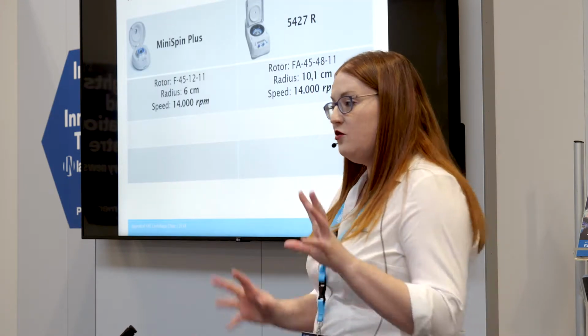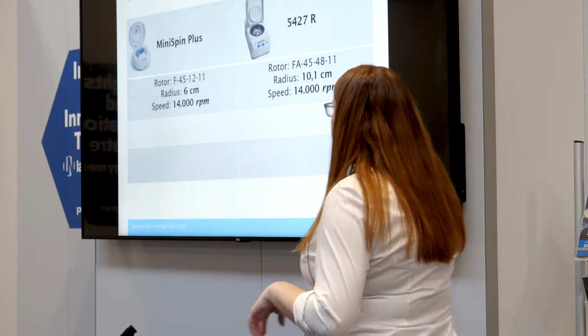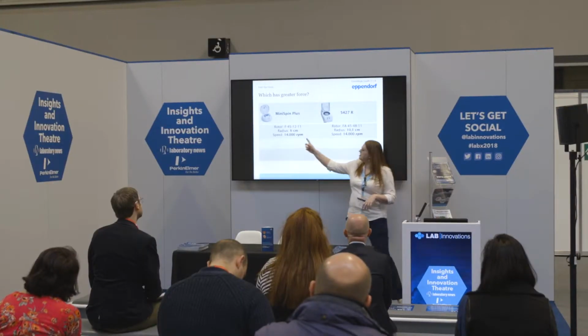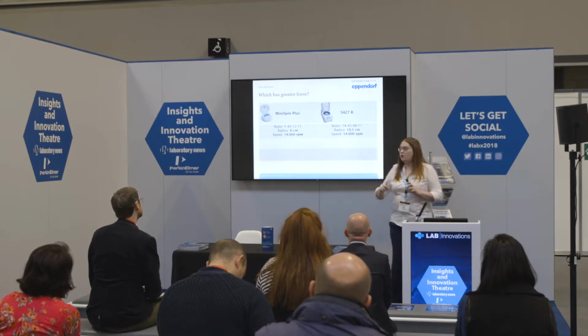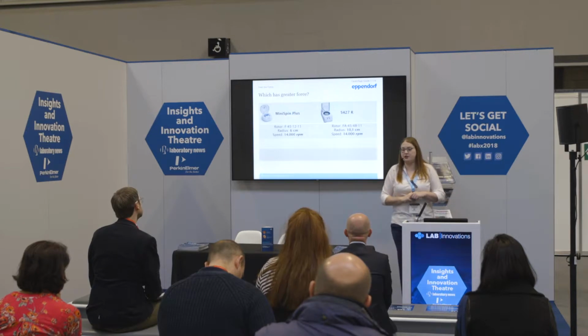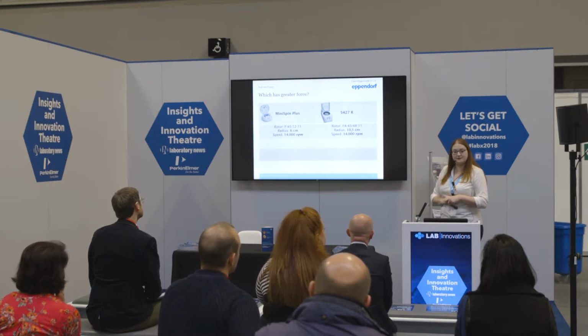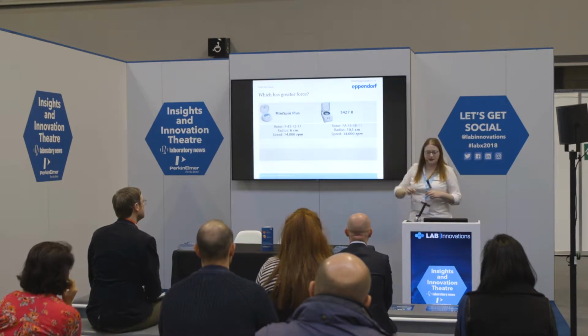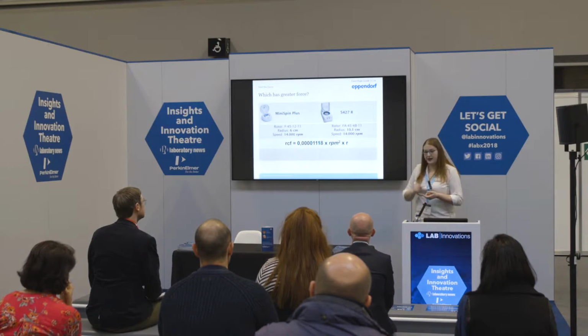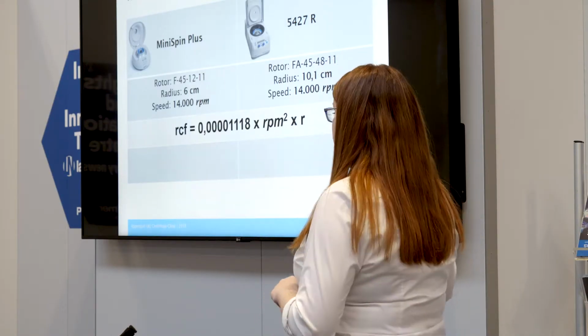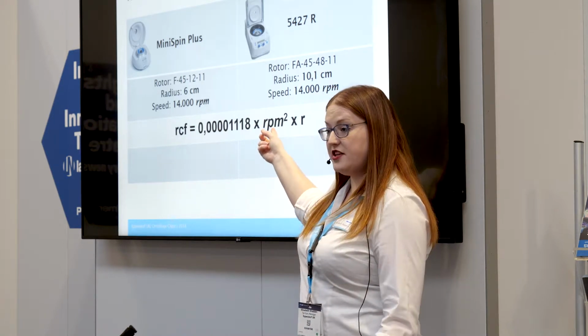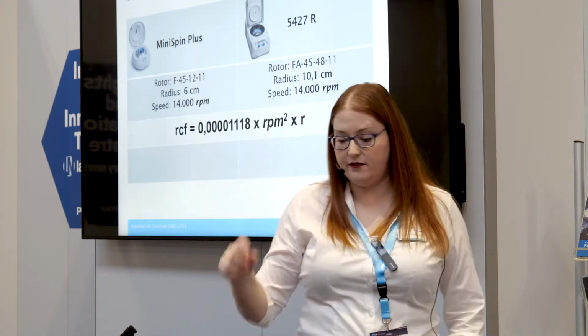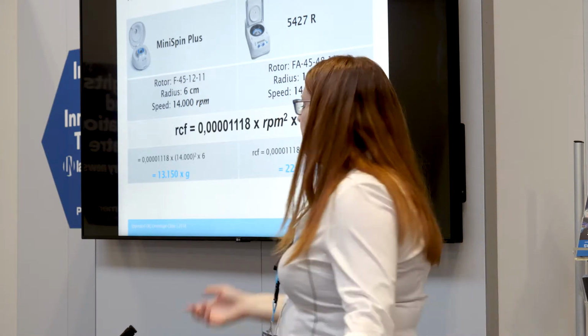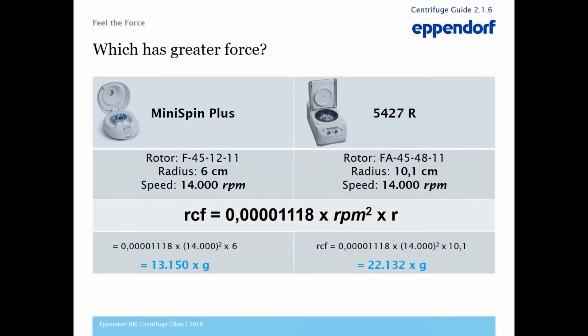So, you're going to actually have to answer a question here. Of these 2, they have the same top speed and they take the same size tubes. Which one is going to be applying the most force to the tubes? Anyone want to take a guess? You're saying the 5427? So the calculation you have to do is to calculate the relative centrifugal force, which, as you can see, takes into account the rotations per minute, the speed, and also the radius of the rotor. So then when you do the actual calculations, the mini spin applies 13,000 G onto the sample, whereas at the same speed, the 5427R is applying 22,000 G to the sample.